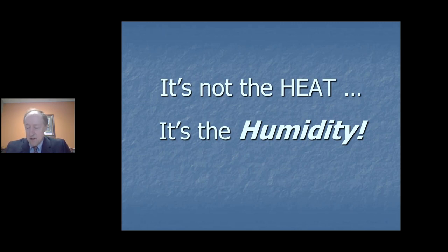Shalandra, let me just kind of in general, although I'm not familiar with what that type of room is, but any type of room, whether it be a surgery suite, a clean room, a lab, an office room, what are the criteria? The two things that you need to ask your client when you're starting to design your building: what are the conditions? What's the condition of the space that you need to maintain? And you plot that out on your psych chart, and you can see the absolute moisture level and dew point or humidity ratio that you need to maintain in that space. And so that's the first point. And then obviously you'd want to know, is this critical all the time or just when it's occupied, or what about when it's unoccupied? So ask all of those types of questions.